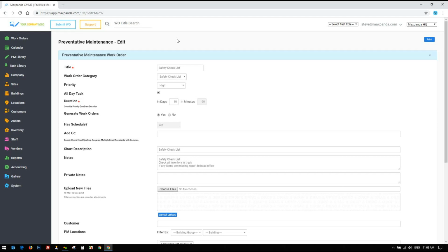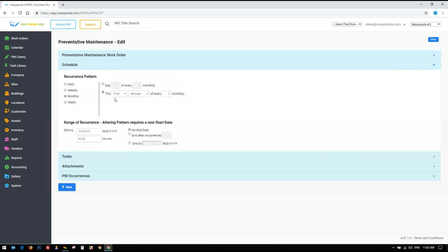Because if somebody comes in and says, we're having a staff meeting the first of the month on the 3rd, and I'm going to calibrate mine while I'm here, and then the next month it kicks off on the 1st and says you have 21 days, 3 weeks. Well, they really don't. That's a complicated floating thing, and it has to be once every 30 days. Same will fall with the yearly things. Once a year, you can't say once a calendar year. It has to be within a year of the last time it was done.